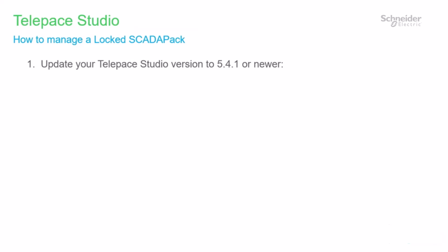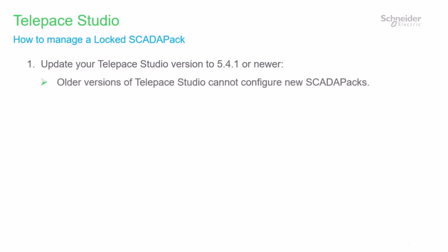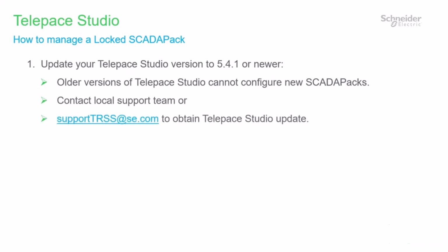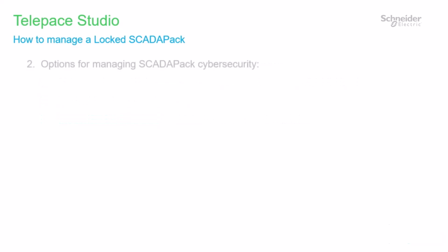To unlock your SCADAPack and resolve this issue, you will need to update your Telepace Studio version to 5.4.1 or newer. As you may have discovered, older versions of Telepace Studio will not be able to configure new SCADAPacks equipped with a cybersecurity feature. Contact your local support team or this email to obtain the Telepace Studio update.